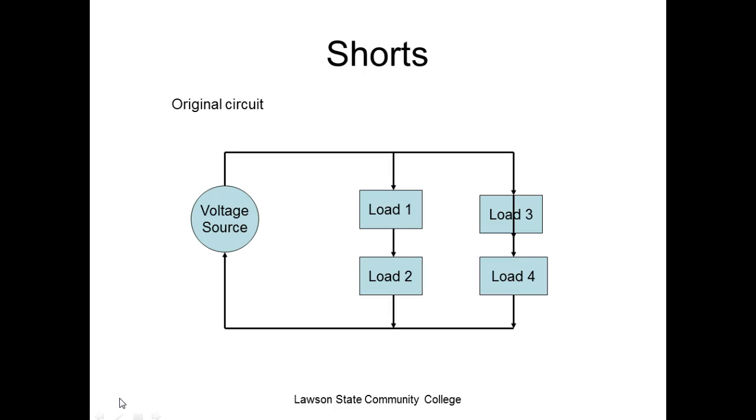What you learn, especially in the National Electrical Code, is that the circuit breakers or fuses they choose are not in there to protect the load. They're in there to protect the conductor. So it's in there for short circuits, not for overloads. This is why every once in a while you'll have an appliance, like a hairdryer, that burns up in your hand and your breaker doesn't even burp, because it's still got resistance and it's still not pulling enough current to endanger the wire. So most overcurrent protection devices are in there to protect against short circuits, not overloads.